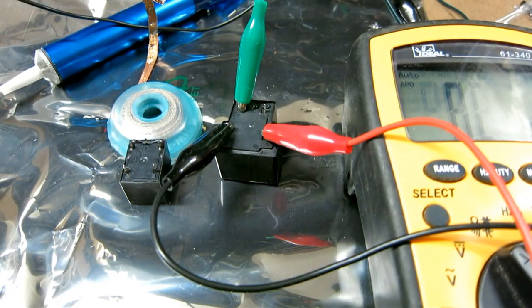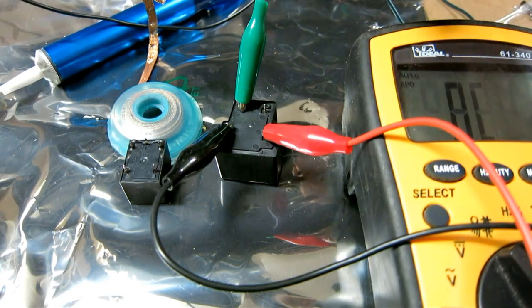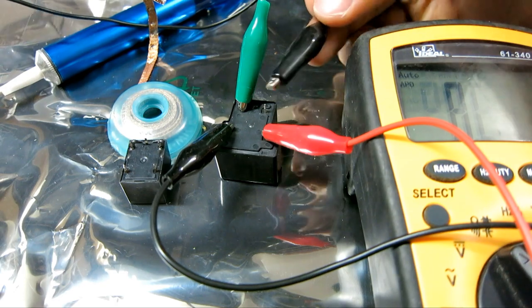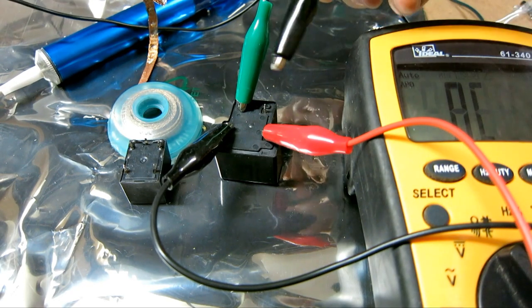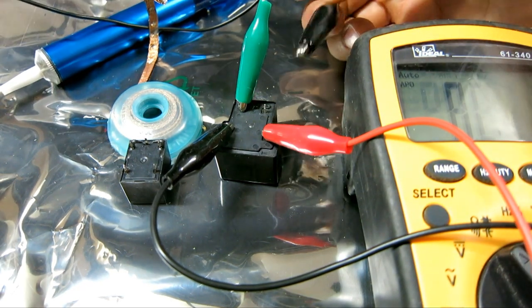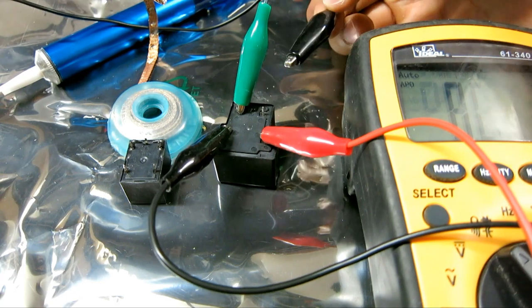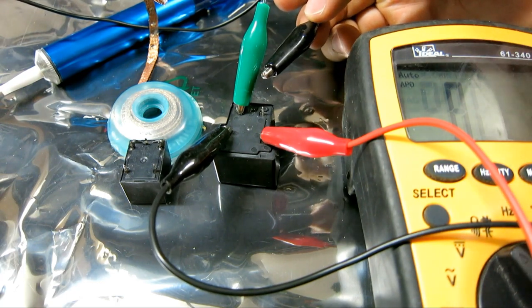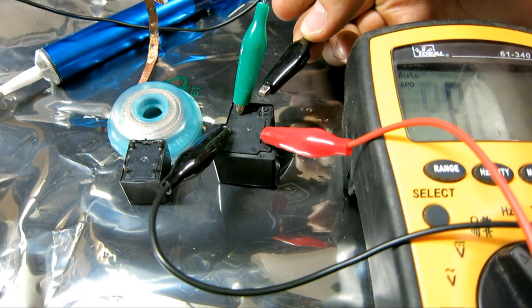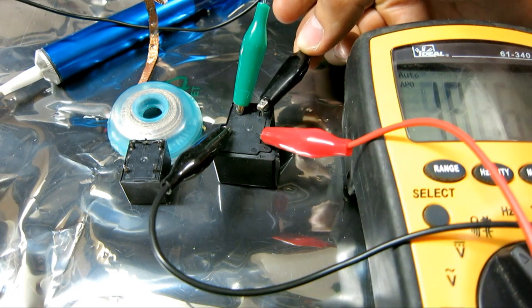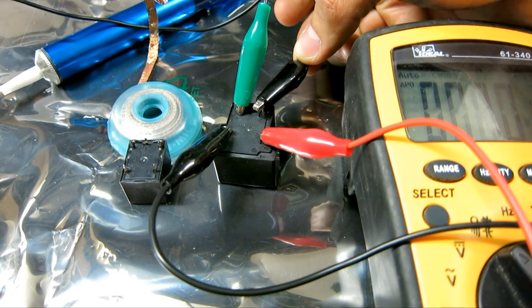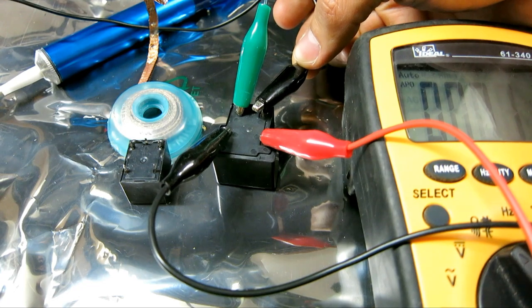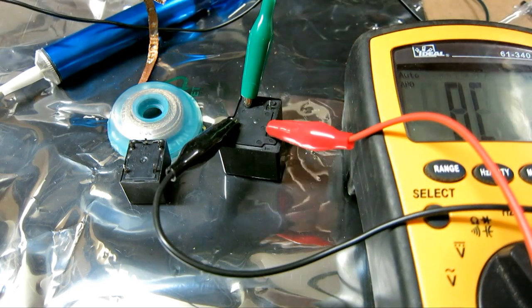So right here I have the normally open relay, the big one. I have the black and red wires connected to my digital multimeter to measure resistance. And I have 18 volts going to here, DC. So if I touch this, I can see it click. And I have zero ohms, which means that this normally open relay works.